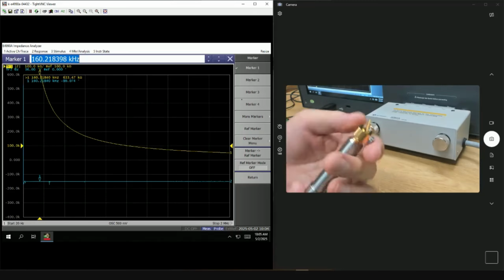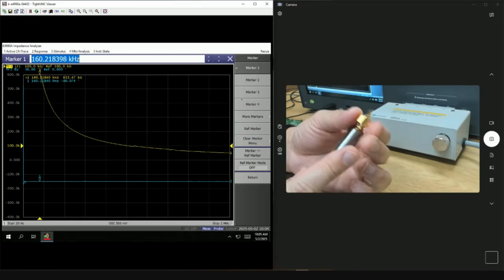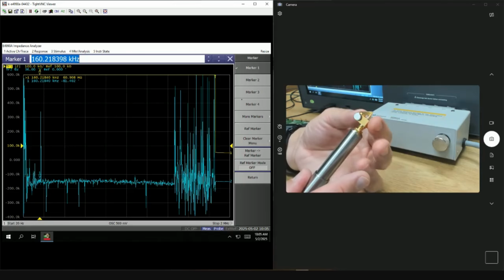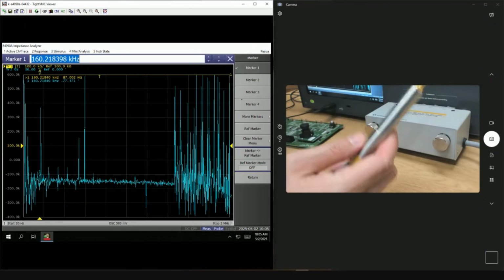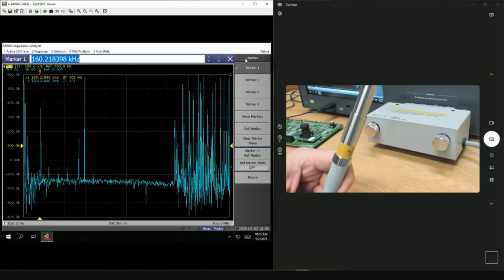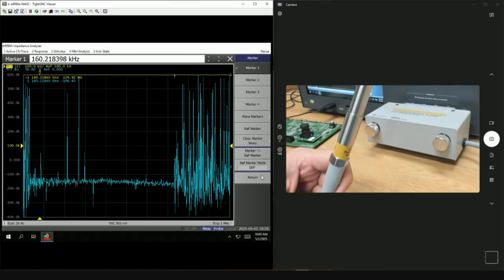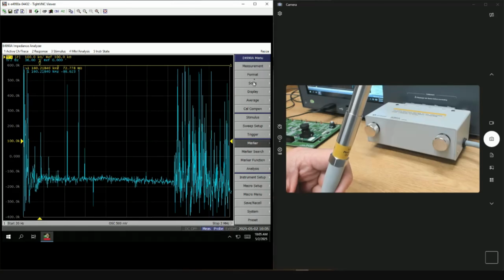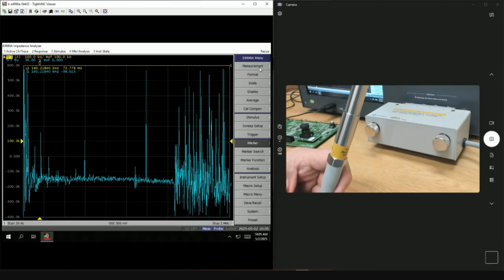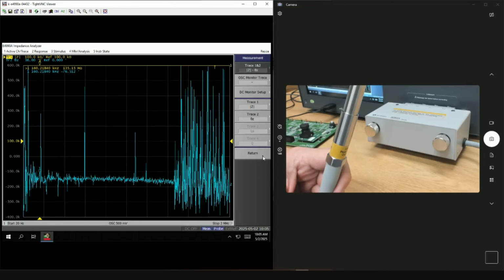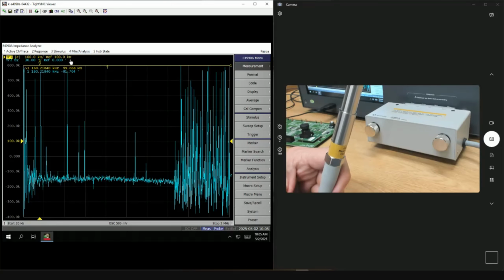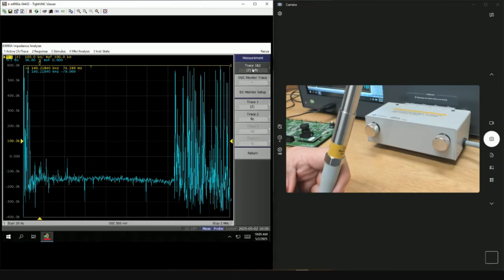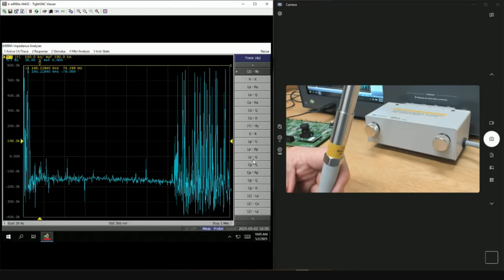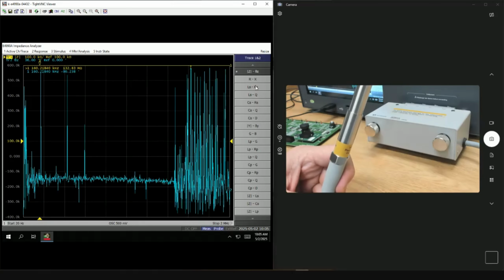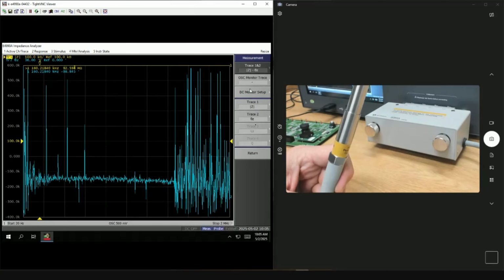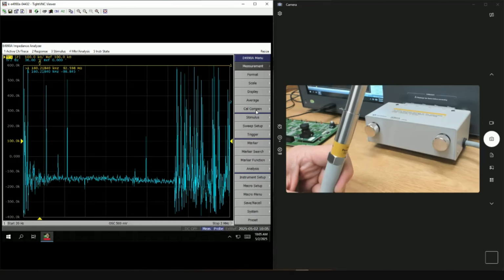So the first thing is to remove this, because we want to calibrate until the end of the prober without the probe head. That's the first step. So let's go to calibration, return, and we're going to go to measurements. By the way, before you do anything, let's say this is a measurement where you want impedance and also phase. This is where you can change impedance, phase, or select any other measurements of interest here. For this exercise, I just change that, and then the next thing I want to do is cal component.